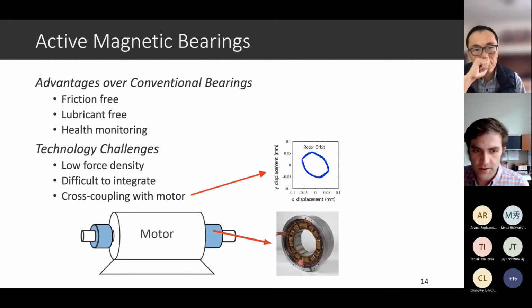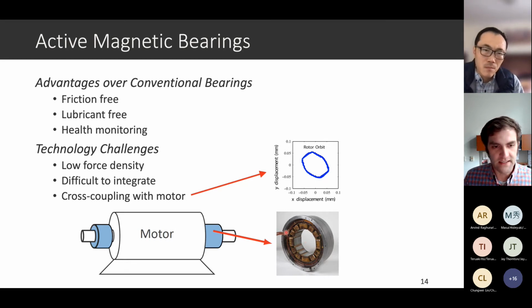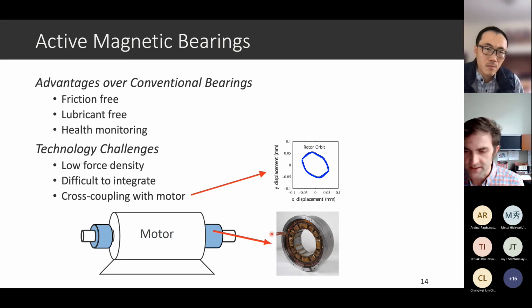It looks a lot like a motor, and it functions in a sense like a motor, only it does not produce torque, it produces radial forces. So this is the stator of a magnetic bearing. The shaft goes through here, and what the stator does is create X and Y forces on that shaft, or radial forces on that shaft. And you can see it looks like a motor in that there's laminated steel, there are coils wrapped around teeth, and not shown here, but you'd have a power electronics cabinet next to it, with power electronics driving currents into it.